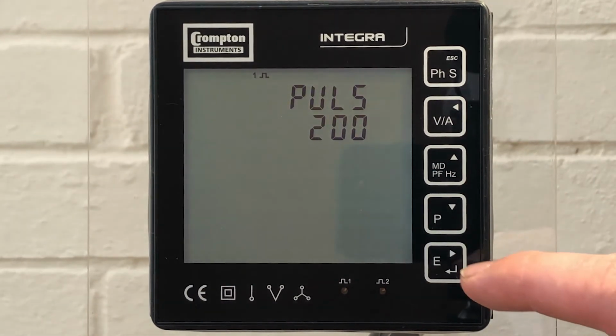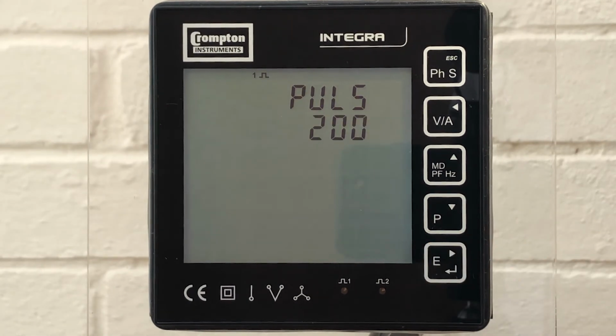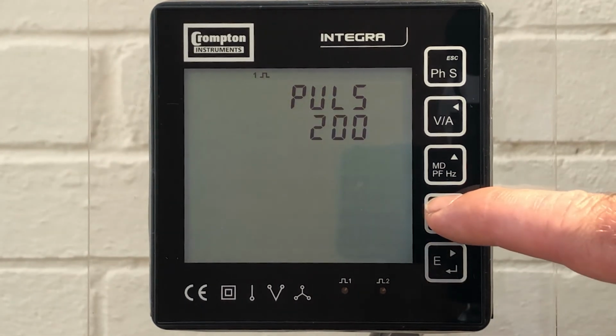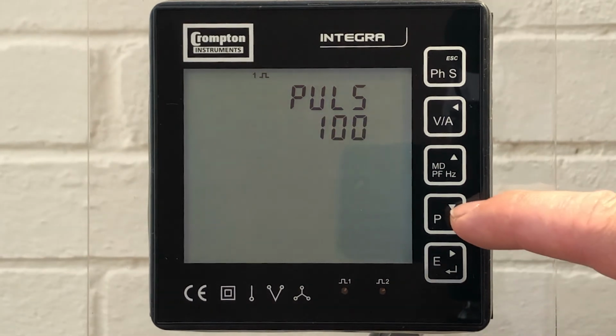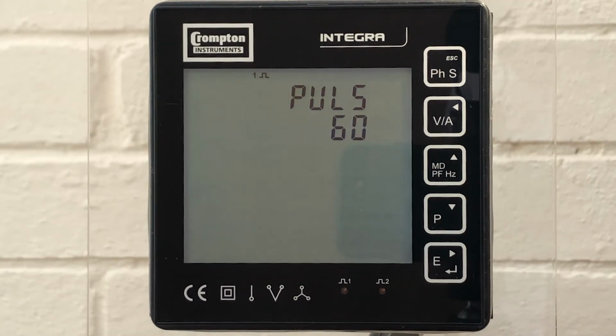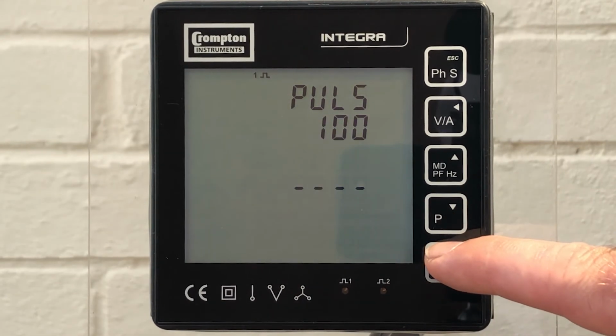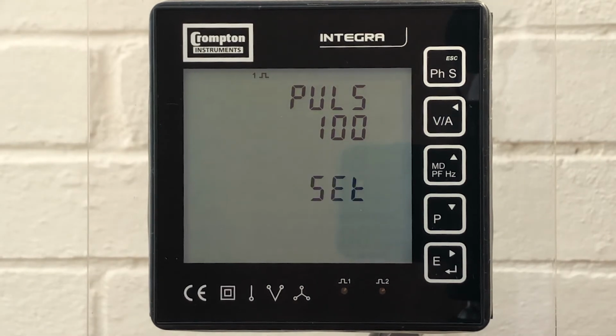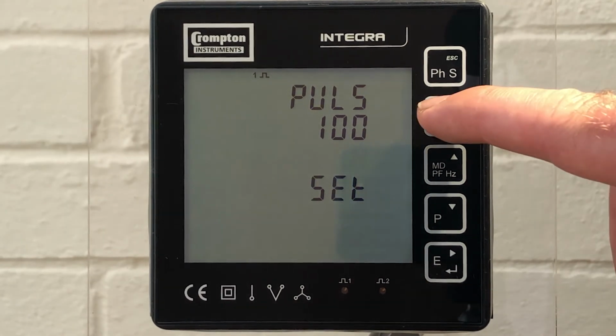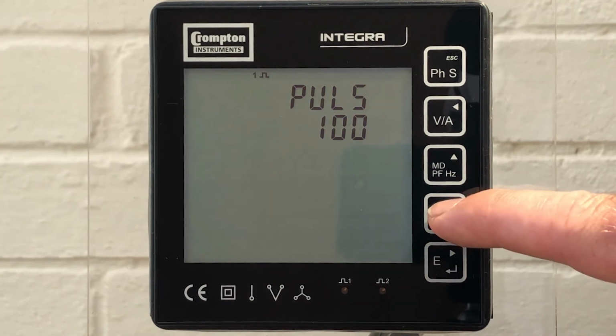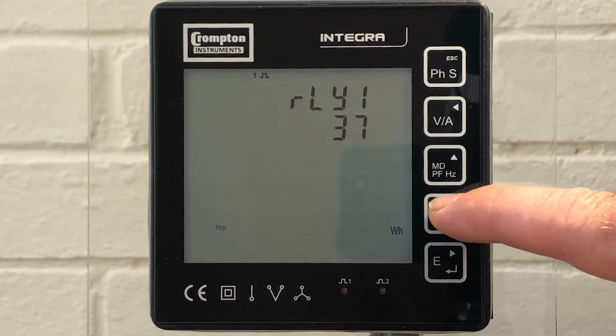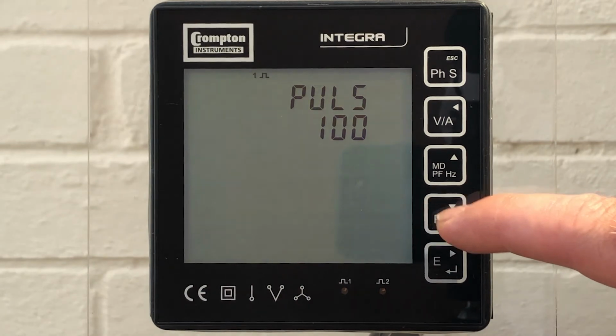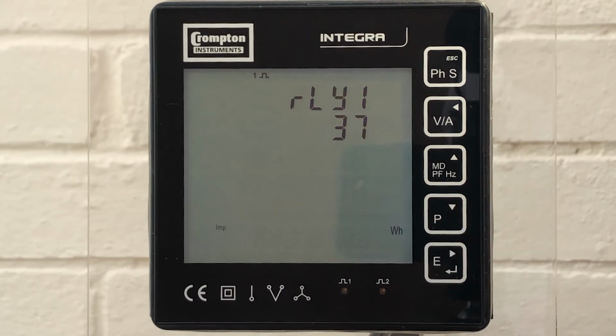Our next setting is for the pulse duration, and the available options are either 200, 100 or 60 milliseconds. We'll set ours at 100 milliseconds. And we can now review all of our pulse relay settings by arrowing down through the settings that we've put into place and move on to our next setting.